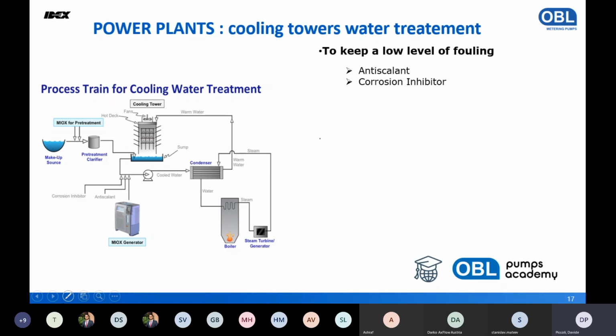But again, the need to dose needs to be very, very precise. And there is always an automatic control with sensors put inside the cooling tower that give signal to the pumps to adjust precisely the amount of chemical to be dosed. It's also very important to keep the pH very well balanced.